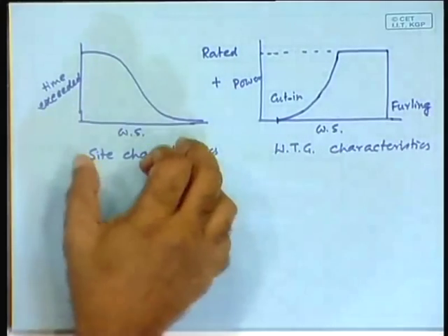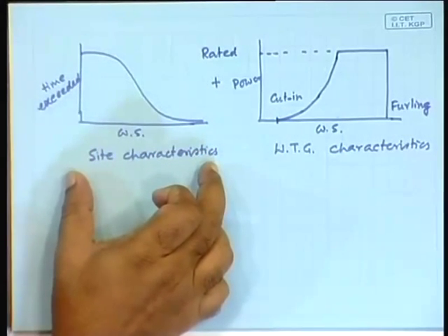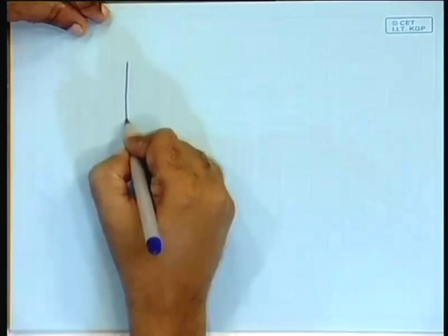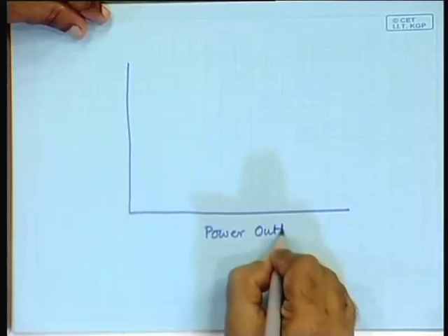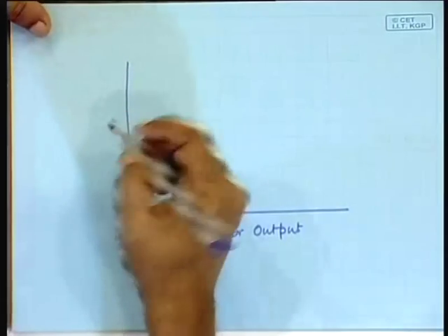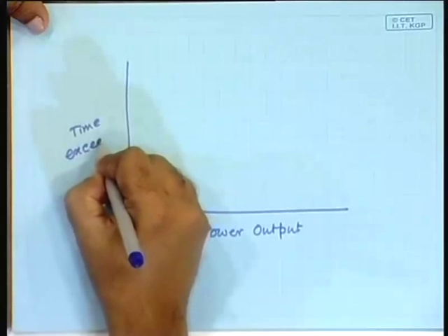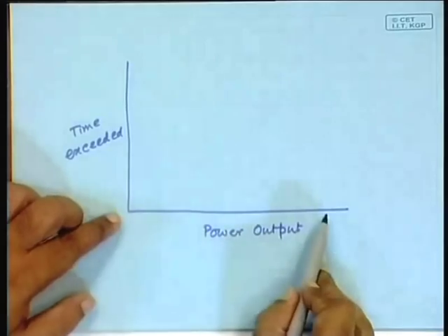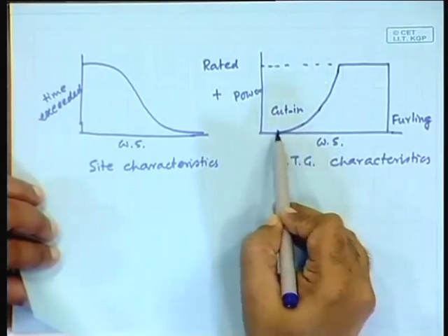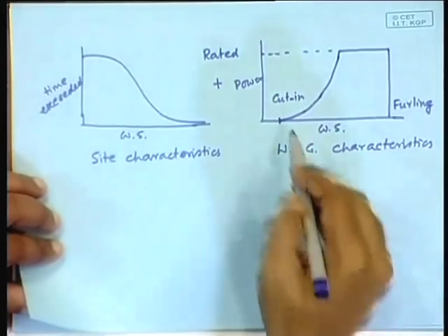We have the site characteristic and the generator characteristic. These two have to be matched by obtaining the power duration characteristic — power output on one axis and time exceeded on the y-axis. The power output for any value of wind speed is given by the generator characteristics. Following the cubic characteristic, the power is k times v-cubed, where k is essentially half-rho times area times Cp.